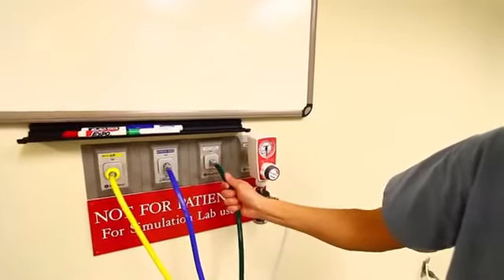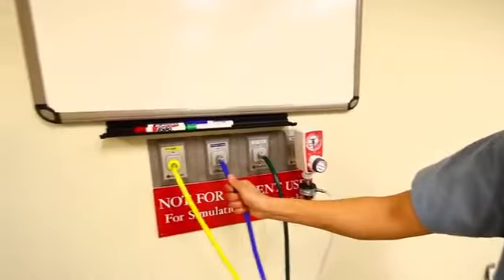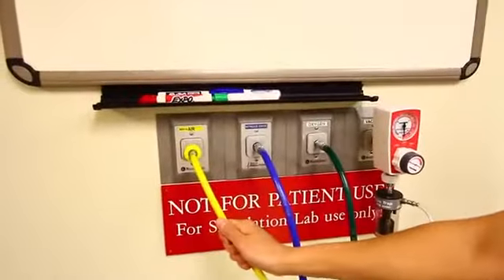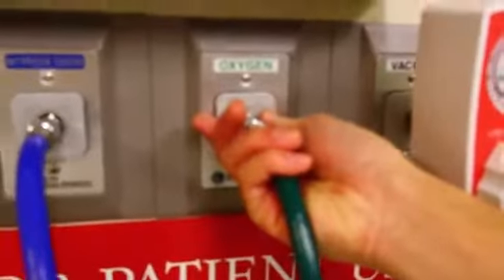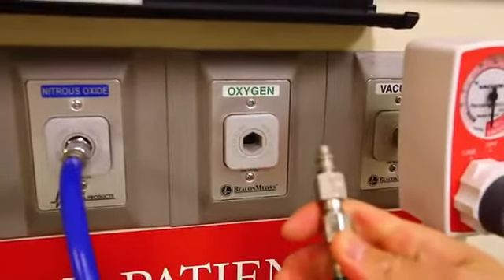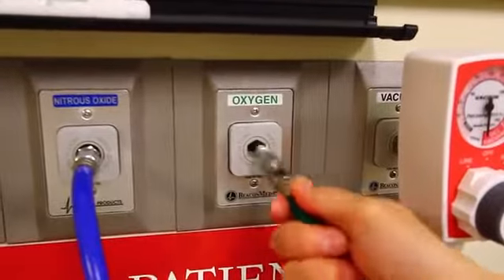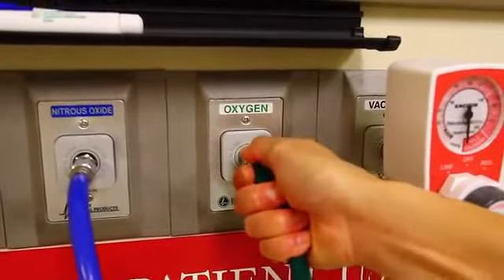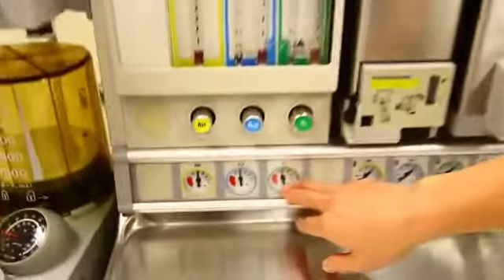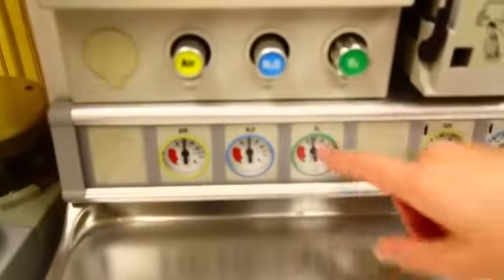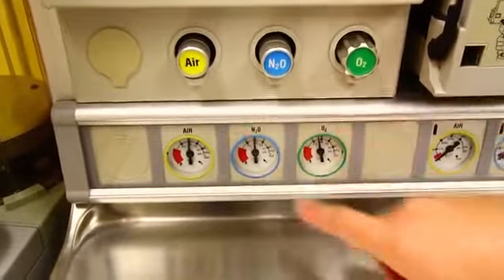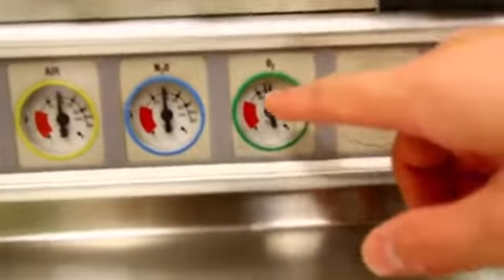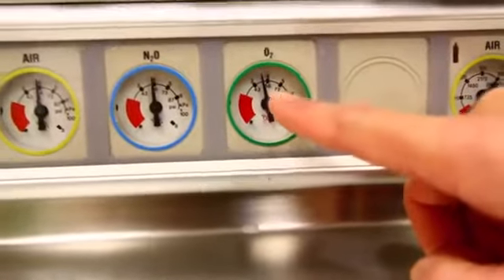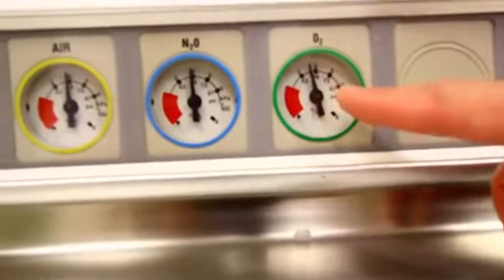Oxygen, again, is usually denoted by green, nitrous oxide, blue, and air is yellow. To disconnect one, you'd actually push it in and release. And in order to connect it, you have to push it back in. Note the pipeline gauges do not have a picture of a cylinder and have much lower pressures. You need to verify these gauges read about 50 psi.